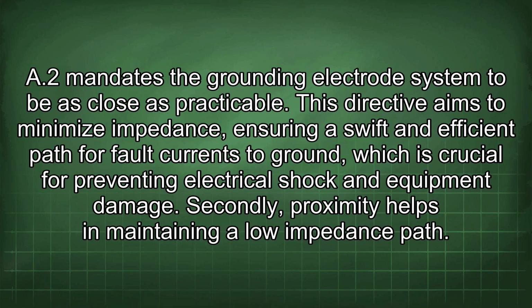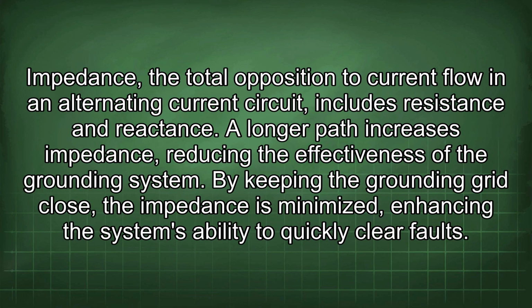Secondly, proximity helps in maintaining a low impedance path. Impedance, the total opposition to current flow in an alternating current circuit, includes resistance and reactance. A longer path increases impedance, reducing the effectiveness of the grounding system. By keeping the grounding grid close, the impedance is minimized, enhancing the system's ability to quickly clear faults.